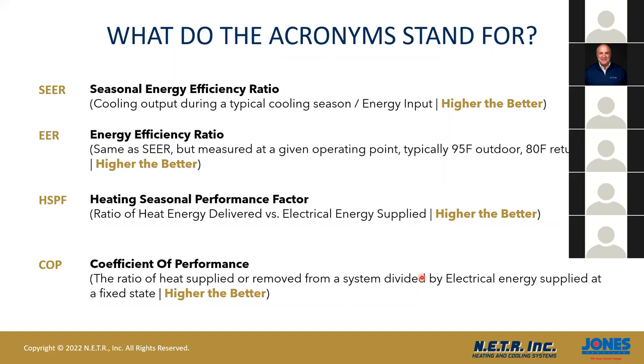And the same thing with the heat pump. We're seeing inverter-driven heat pumps from hyperheat systems or basic air source heat pumps as high as 30, some as high as 40 with different manufacturers. So don't get caught in the myth that a 13 SEER heat pump is cheaper, it's less money. Well, there's a reason why it's less money. It is going to cost you more to operate. So you have to be very, very aware of the SEER rating. What is the SEER rating of the system?